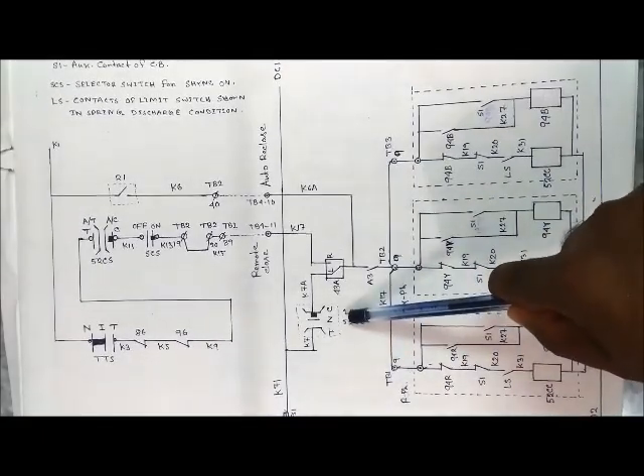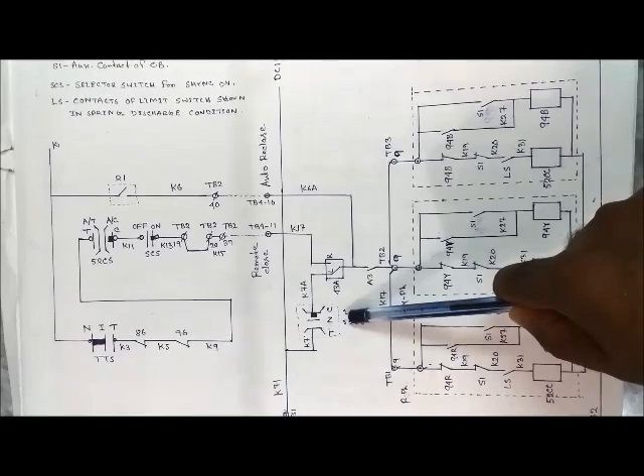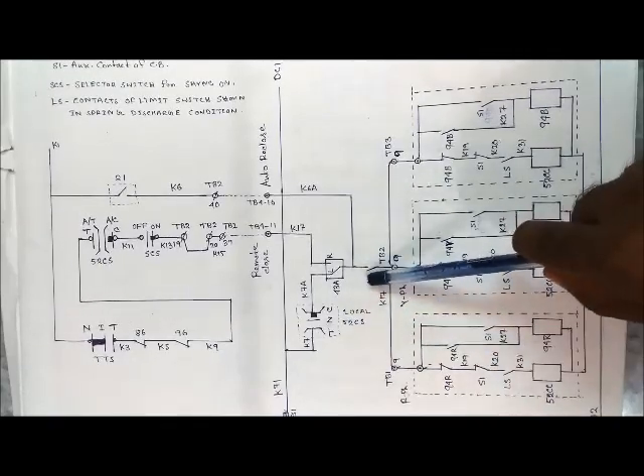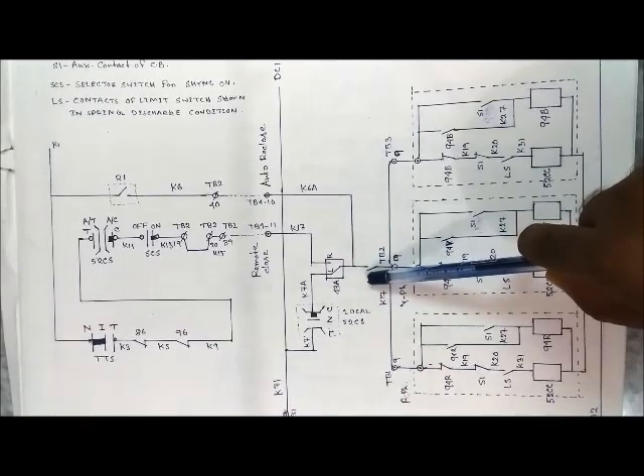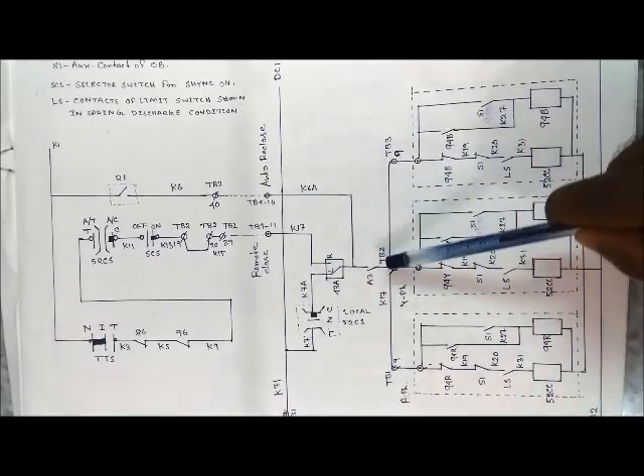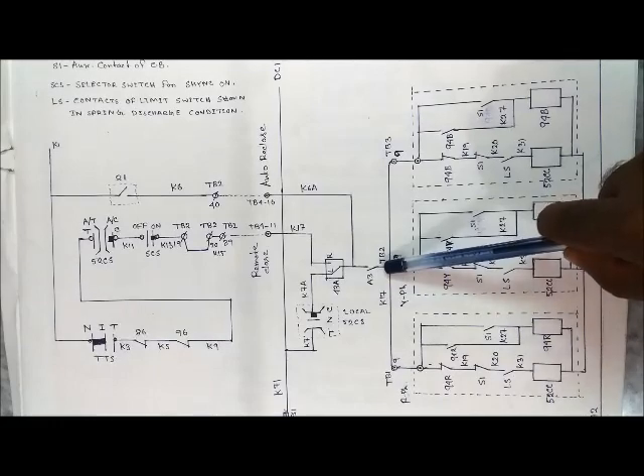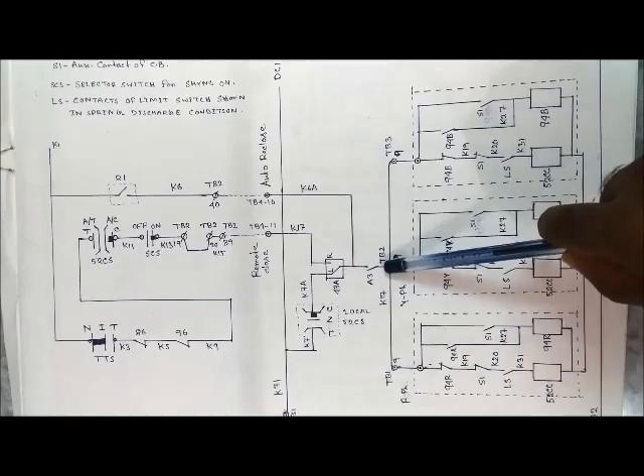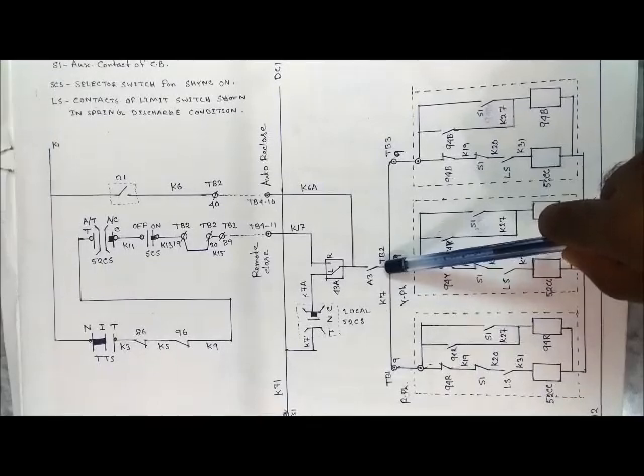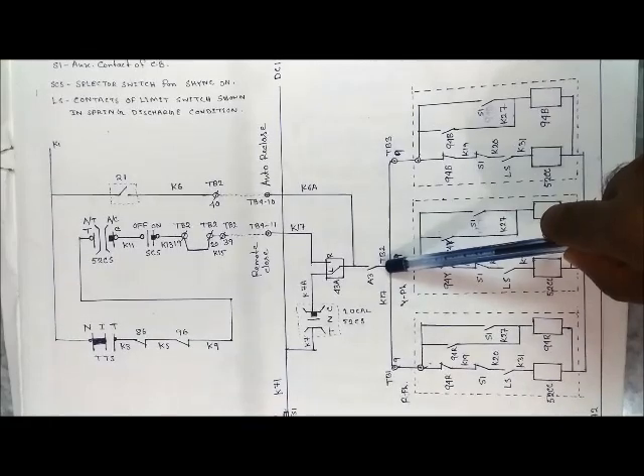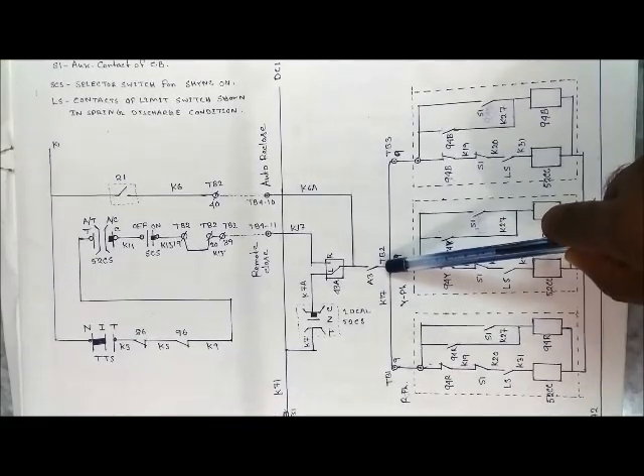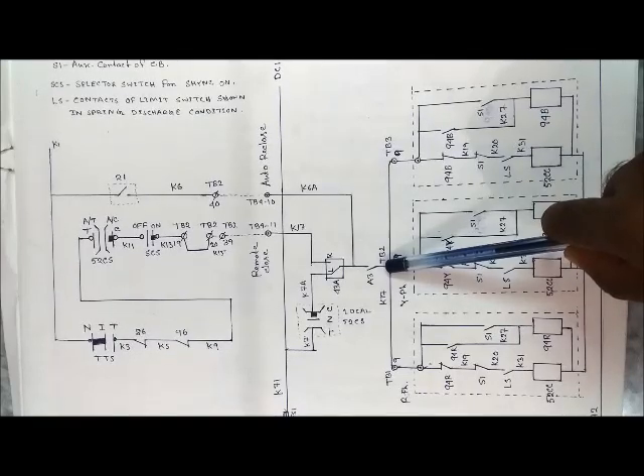TNC is the local control switch of the circuit breaker — that is, trip-neutral-close control switch. 43A is the local/remote selector switch. A3 is the contact for SF6 low gas pressure lockout. This contact is shown under lockout condition: if the gas pressure is below 7.8 bars, this contact will be in the NO position.